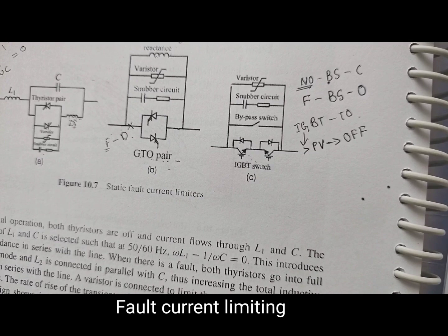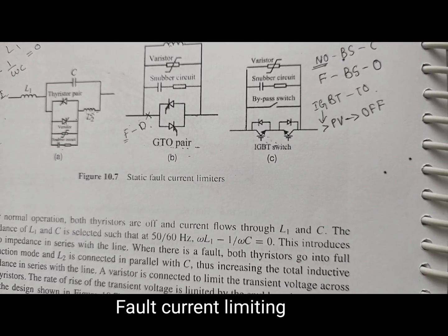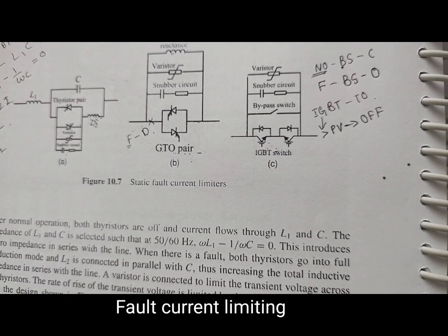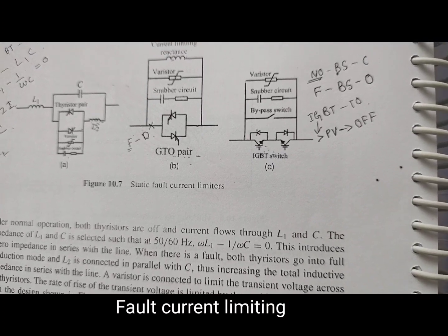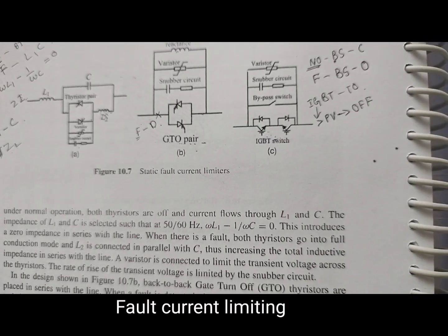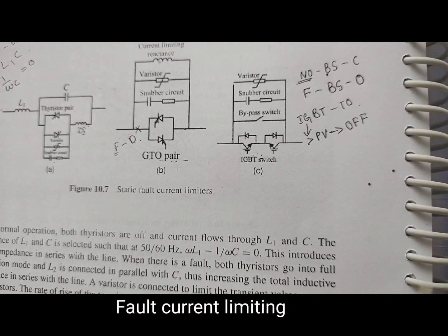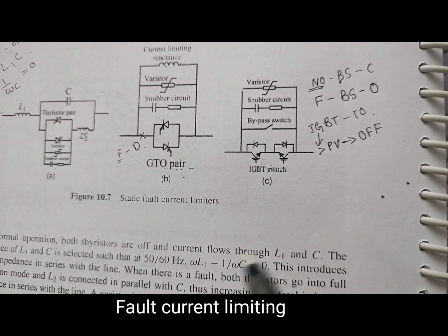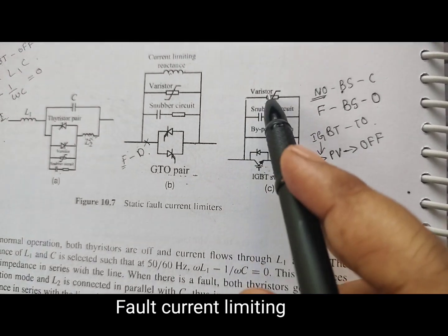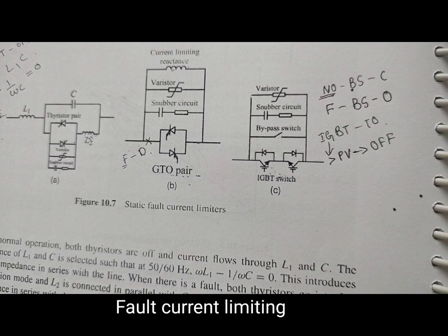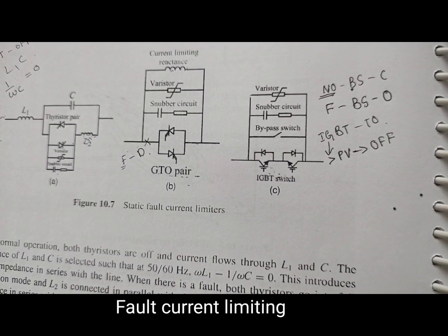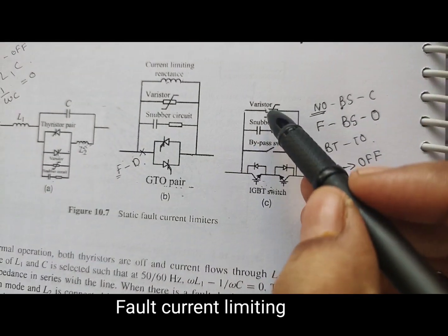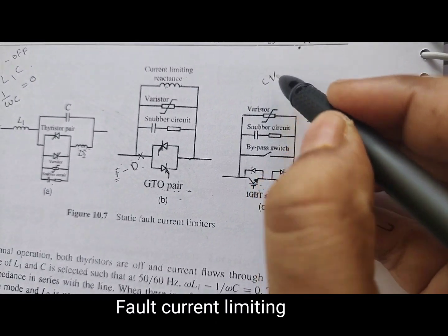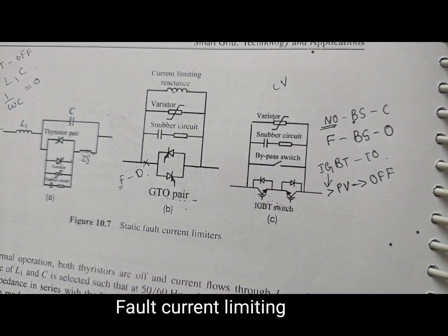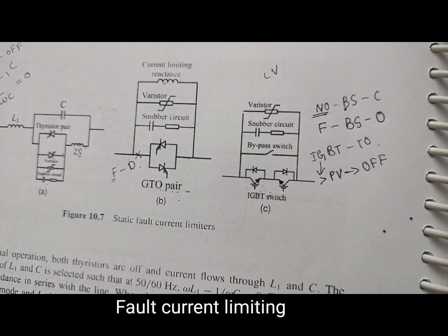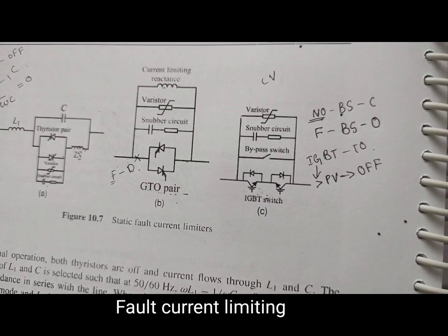When the fault current reaches the preset value, the fault current flows through the varistor. The clamping voltage of the varistor is set to be higher than the peak supply voltage.